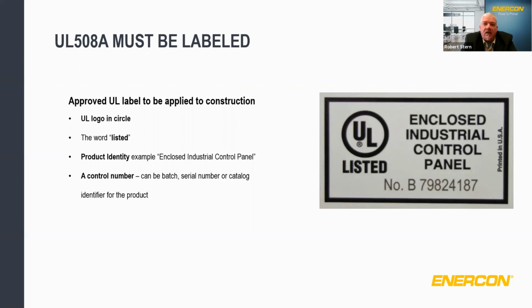Labeling requirements for the 508A standard: you'll see an example on the right. You have to have the UL logo with the circle, the word listed, a product identity, which says whether it's an open panel, an enclosure, or an enclosed industrial control panel, and a control number. The control number is specific to the panel shop. It could be a serial number, a catalog number, or just a product identifier, but it is specific to that panel builder. Next slide.